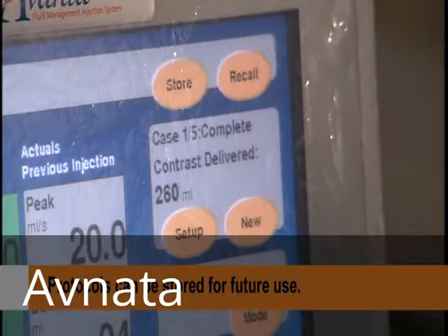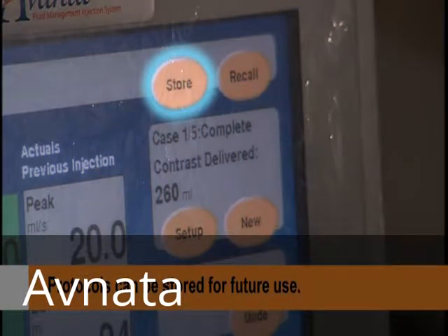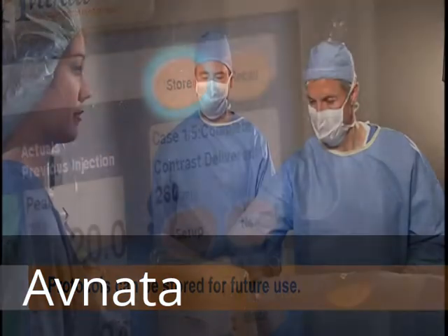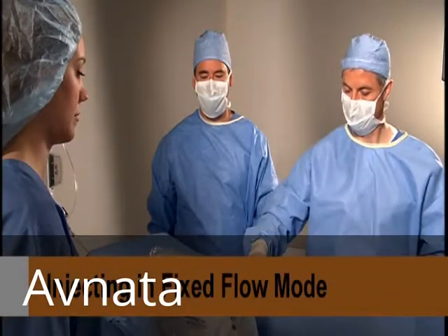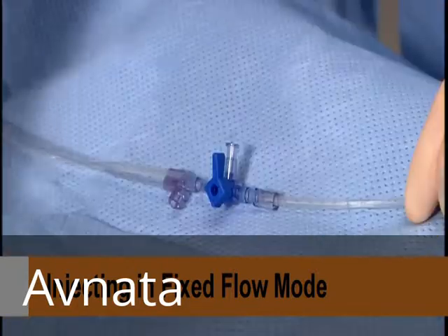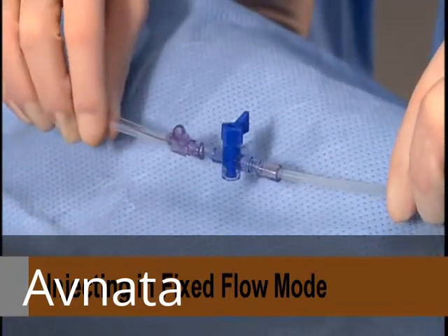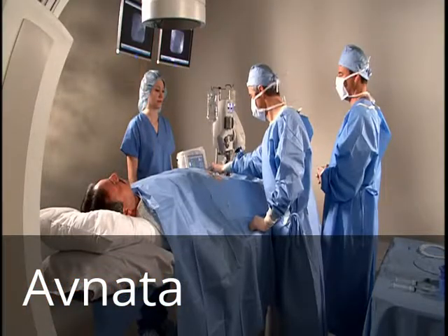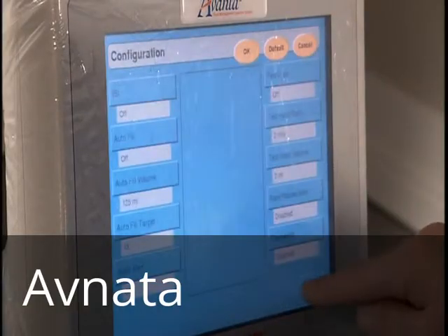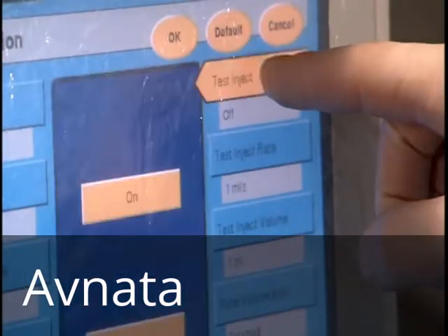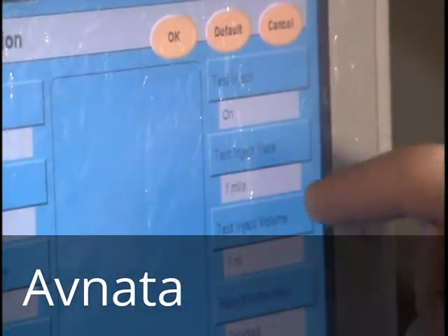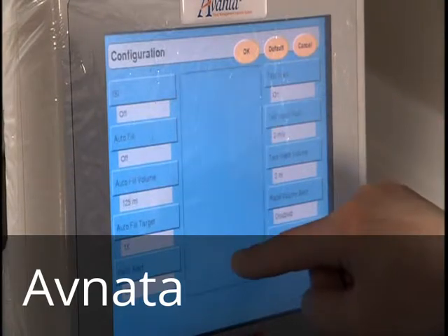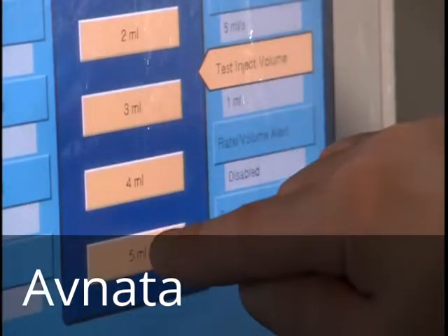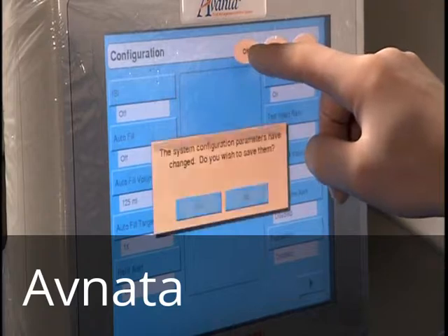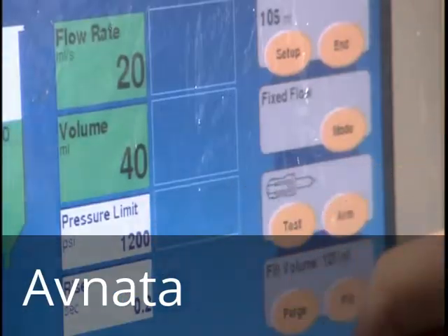Once an injection is complete, you may save the protocol in the system memory for future use. When arming the injector in fixed flow mode, verify that air is purged from disposables and the injection parameters are correct. Performing a test injection is optional. A test injection delivers a limited amount of contrast, referred to as a puff, at a set flow rate and volume to verify catheter placement. Test injections are delivered at fixed flow only and programmed from the configuration screen.